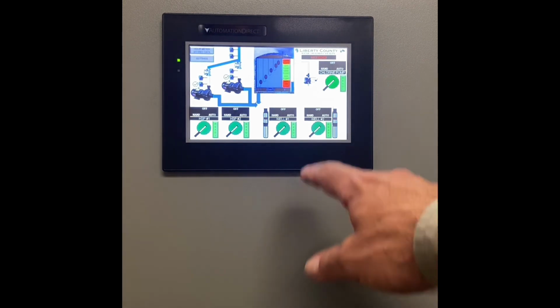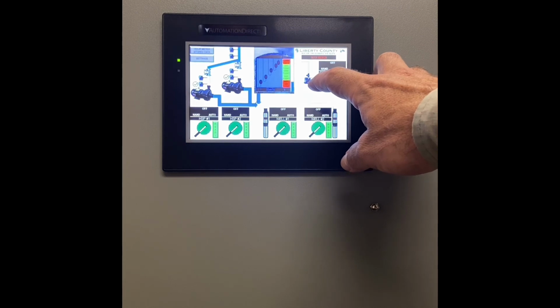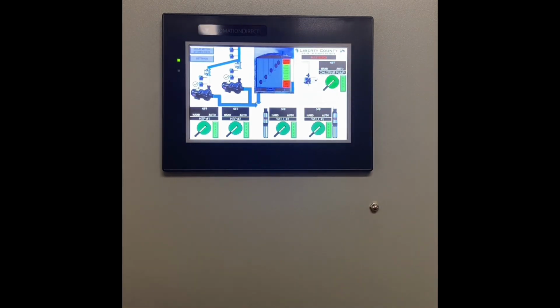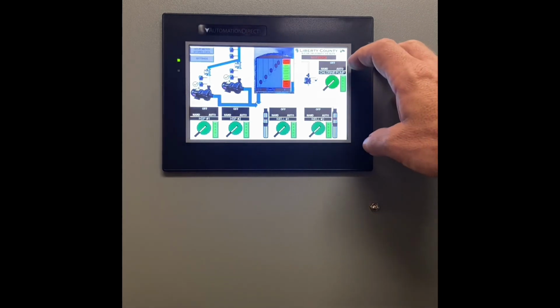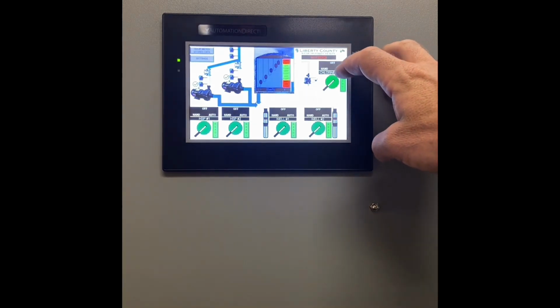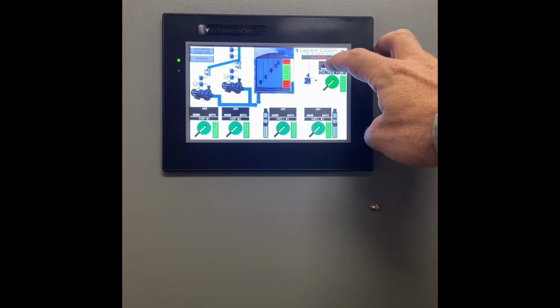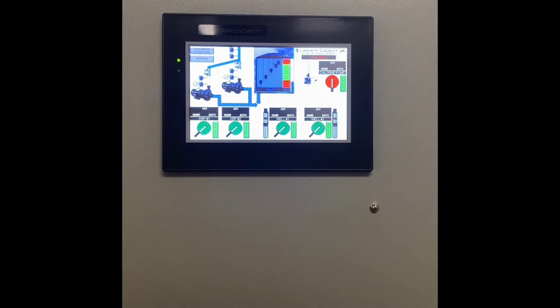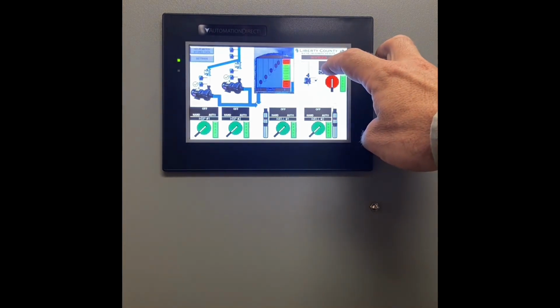As we move across the screen, you'll notice that we have a chlorine pump. That chlorine pump will come on either in manual or in automatic. In automatic, it comes on anytime either well 1 or well 2 is running and we're adding chlorine. We can put it in manual now, and all 5 of my hand-off-auto switches work the same way. If we touch the off, you notice my virtual indicator goes to off. And if we go to hand and I'm quiet, you'll hear the contactor pick up as soon as I touch the hand.